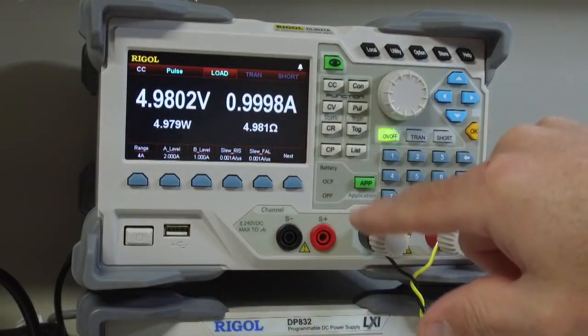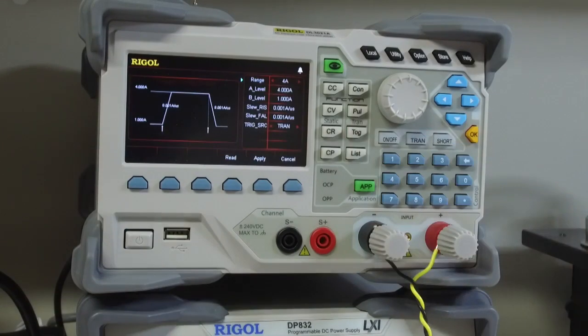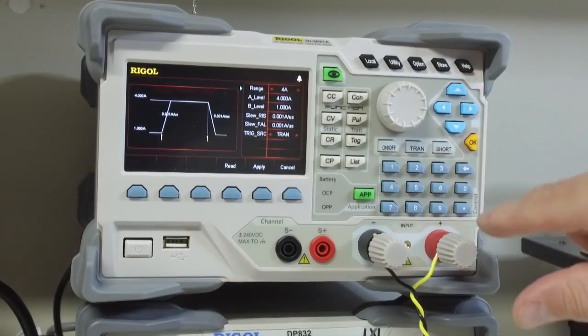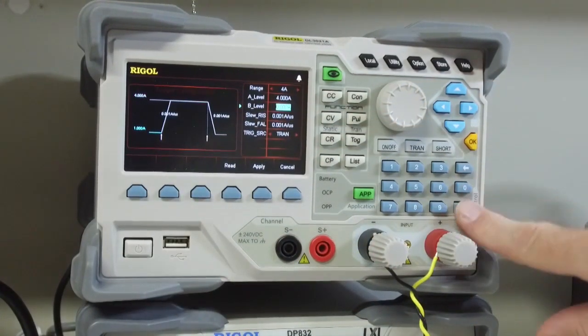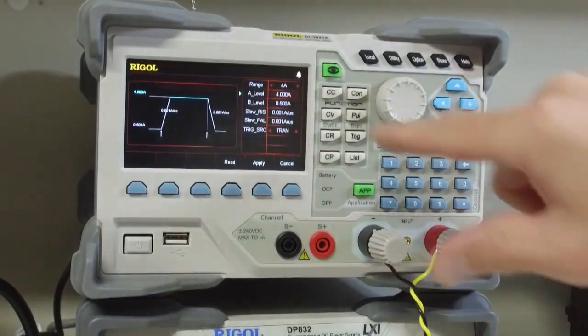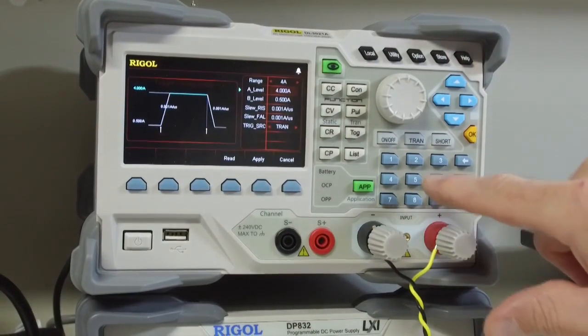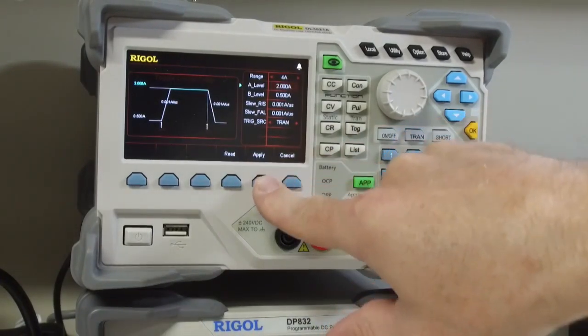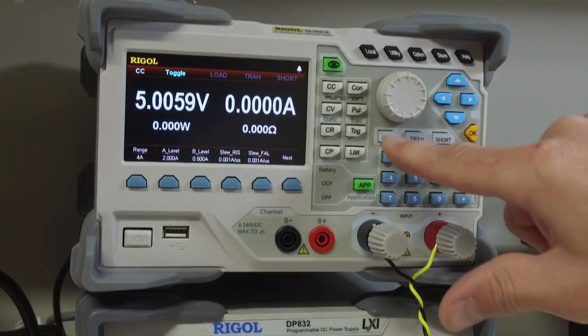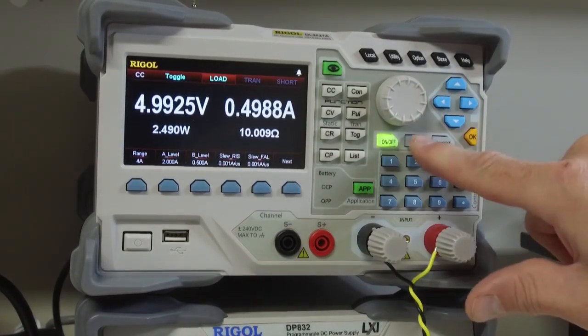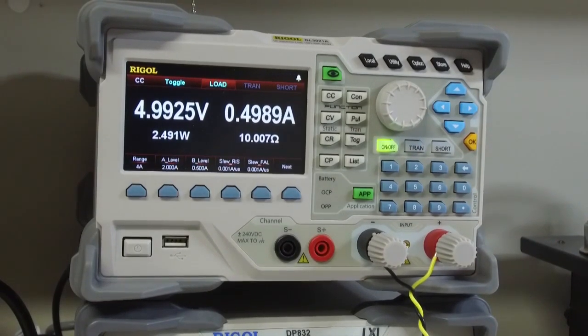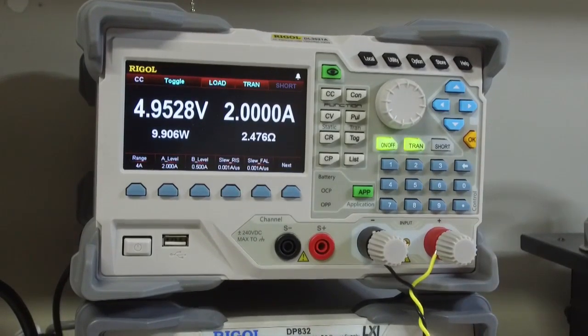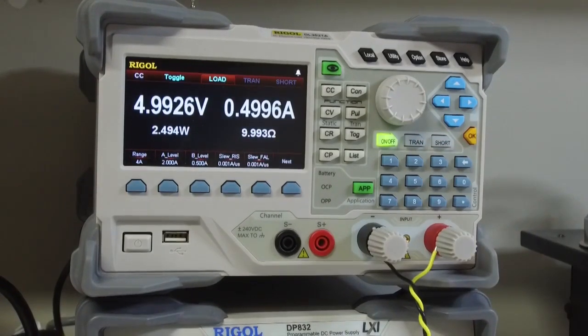Another nice feature is this toggle transient. So I'm going to adjust my steady state to half an amp, 0.5. And I'll set my A level to 2 amps. Apply. So what this is going to do is when I hit the transient button, it will apply that 2 amp load until I push the button again. So here we go. I'll push the transient. There's our 2 amps. I'll push it again and it will toggle off.